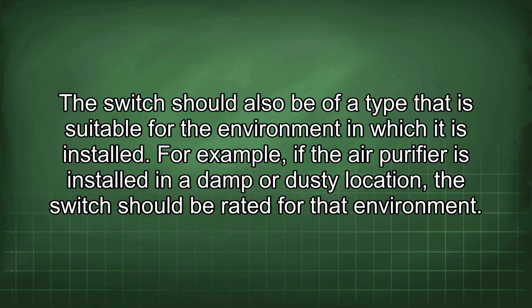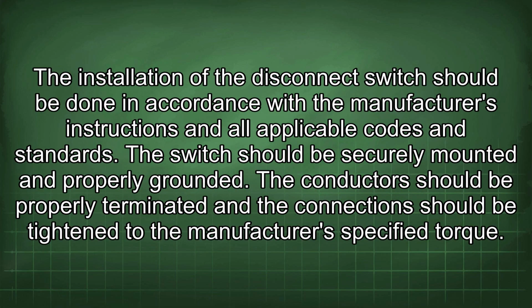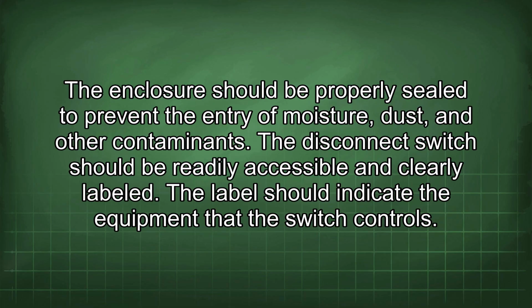The installation of the disconnect switch should be done in accordance with the manufacturer's instructions and all applicable codes and standards. The switch should be securely mounted and properly grounded. The conductors should be properly terminated and the connections should be tightened to the manufacturer's specified torque. The enclosure should be properly sealed to prevent the entry of moisture, dust, and other contaminants. The disconnect switch should be readily accessible and clearly labeled. The label should indicate the equipment that the switch controls.